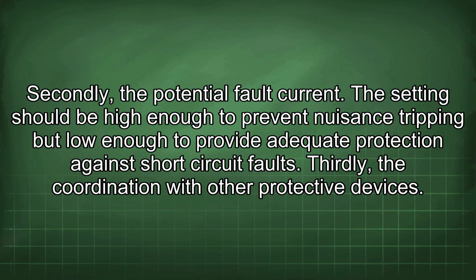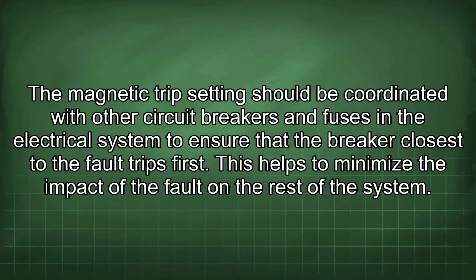Thirdly, the coordination with other protective devices. The magnetic trip setting should be coordinated with other circuit breakers and fuses in the electrical system to ensure that the breaker closest to the fault trips first. This helps to minimize the impact of the fault on the rest of the system.